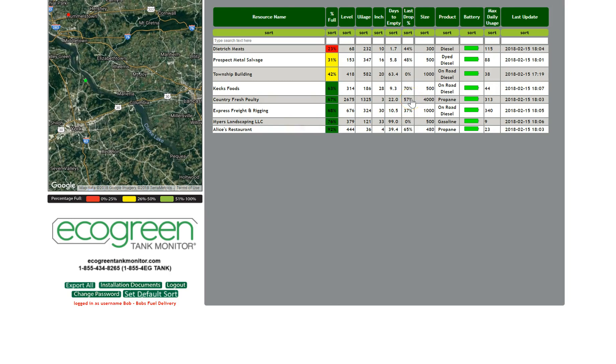Again, these are the same tanks, just in a different format on the right side, with some important additional information, including name of the tank — which is assigned by the user — percent full, level in gallons, ullage (which is how much space is left in the tank), level in inches, a helpful days-to-empty calculation, the size of the last drop or delivery as a percentage, the size or capacity of the tank, the product, the battery level of the monitor — which is diagnostic information — and max daily usage.